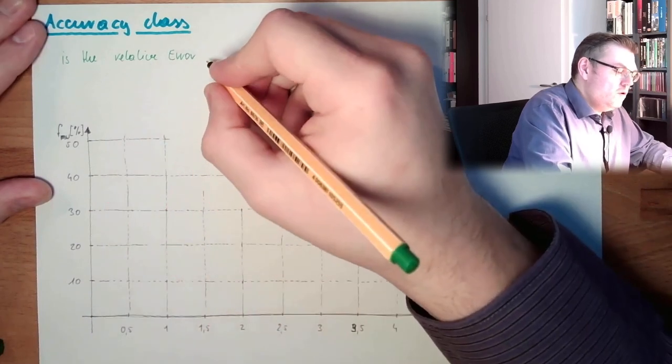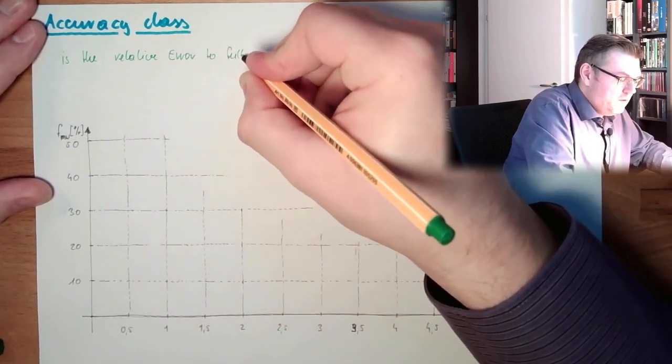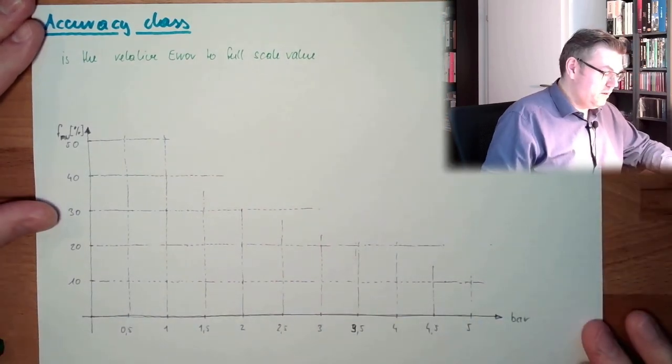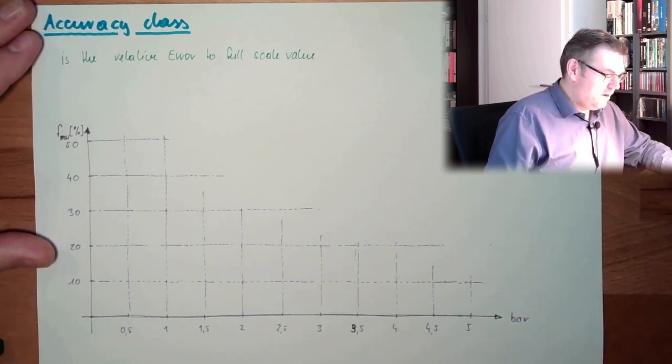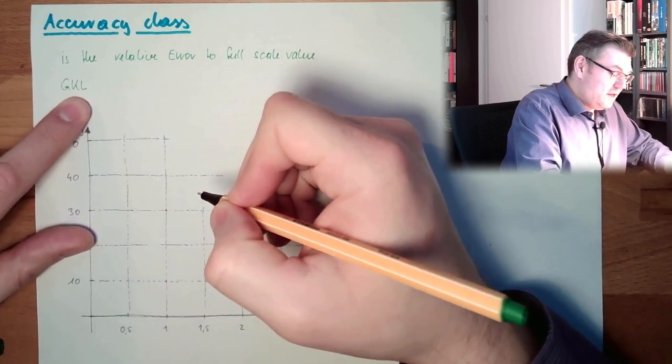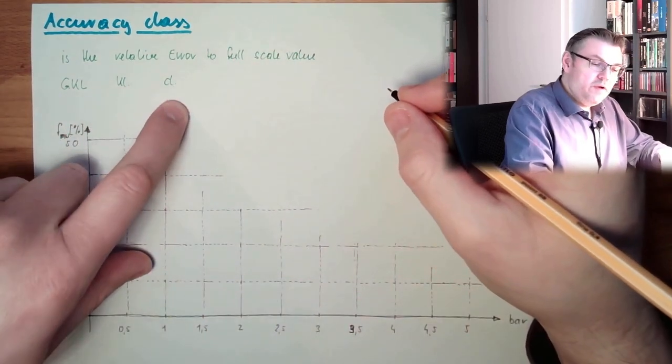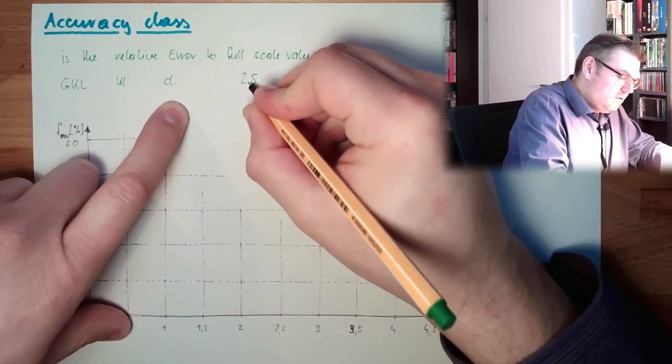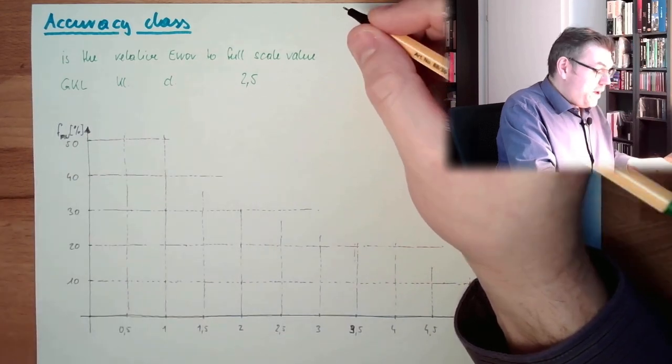So the accuracy class is the relative error to the full-scale value. If we have a class instrument - this is the German abbreviation, Genauigkeitsklasse, it's sometimes labeled like that, or sometimes it's just written class in German or English. If we have, for instance, 2.5, then this would mean we make an error of 2.5% compared to the full-scale value.